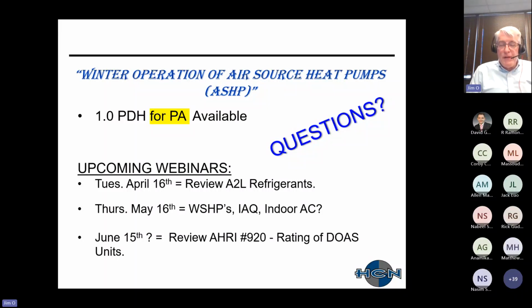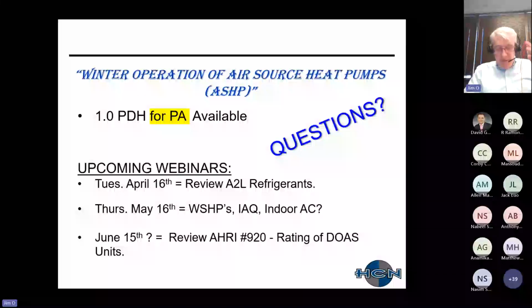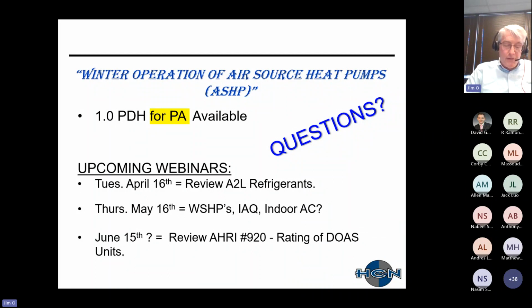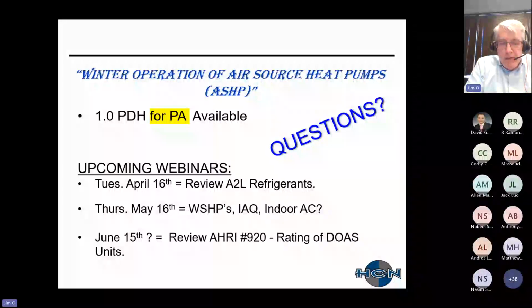Sure. First off, I'm not up to date on experiences using VRF. I'm going from previous jobs or just following the industry. My understanding is that VRF systems, from a heating perspective, don't have such a large derate versus traditional rooftop units. I would attribute that to the VRF systems overspeeding the compressors, running them at 90 or 100 hertz instead of 60. The other thing I would attribute that to is that they have better defrost controls. On the condenser side, they probably have all the same requirements for temperatures, safeties, et cetera.